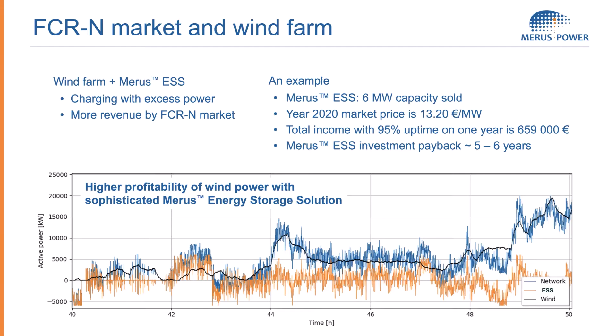So how does this look in a graph? Here we can see the battery energy storage and the wind farm - they are both producing electricity to the grid. The battery energy storage can also, when it's discharging, feed the energy to the network, but when it's charging, it can take the electricity from the network. So if the frequency goes higher, it can charge to bring the frequency back to normal, or if the frequency is getting lower, it can feed electricity to the network.